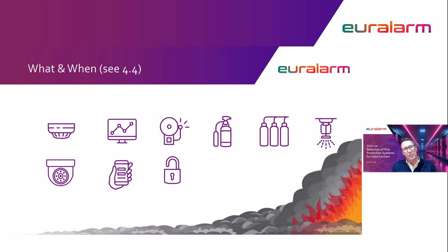For example, if first responders can't get there, or if the fire's grown too large, or it's too great a risk to leave unaddressed, then automatic extinguishing might be necessary, automatically or manually deployed sooner. This could also be prophylactic, and by that I mean the system deployment prior to flaming combustion to ensure there is never flaming combustion. As we go across to the most right hand side of the slide, the last stop, we have sprinklers or water mist, which we must appreciate is not automatic extinguishing, it is suppression or control, and requires the heat bulb to operate.